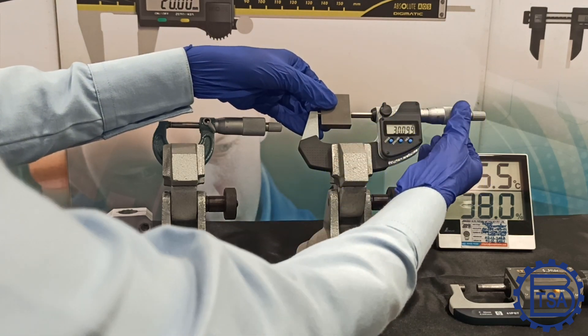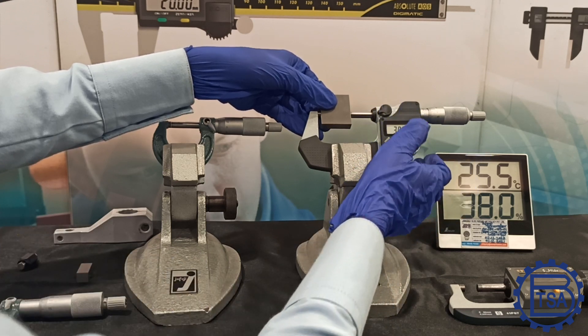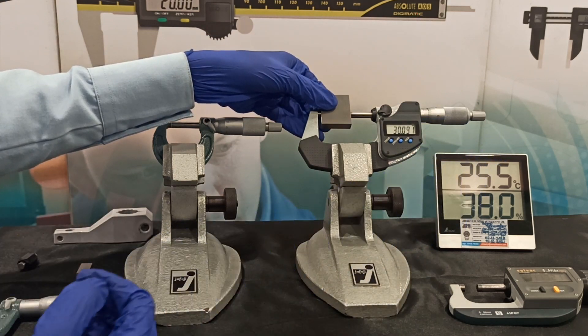Otherwise, the spindle might move and cause error in the readings. One of the most important precautions is to avoid over-tightening of the thimble, which could damage either the micrometer or the item clamped between the spindle and anvil.